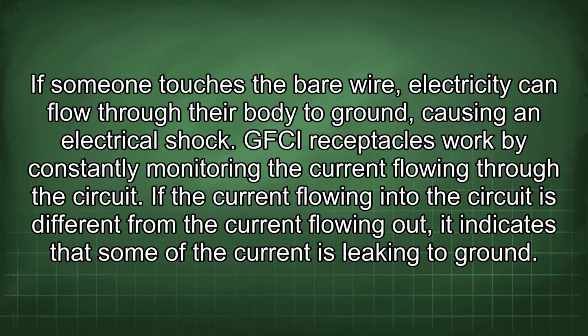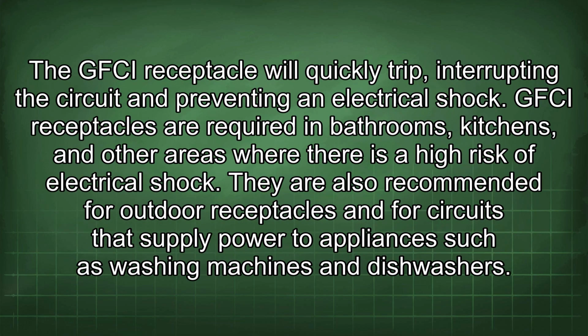GFCI receptacles work by constantly monitoring the current flowing through the circuit. If the current flowing into the circuit is different from the current flowing out, it indicates that some of the current is leaking to ground. The GFCI receptacle will quickly trip, interrupting the circuit and preventing an electrical shock. GFCI receptacles are required in bathrooms, kitchens, and other areas where there is a high risk of electrical shock. They are also recommended for outdoor receptacles and for circuits that supply power to appliances such as washing machines and dishwashers.